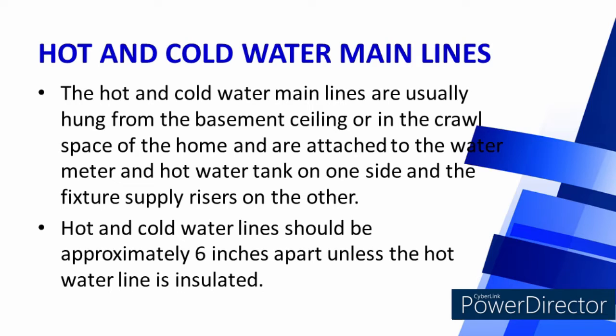The hot and cold water main lines are usually hung from the basement ceiling or in the crawl space of the home, and are attached to the water meter and hot water tank on one side and the fixture supply risers on the other. Hot and cold water lines should be approximately 6 inches apart unless the hot water line is insulated.